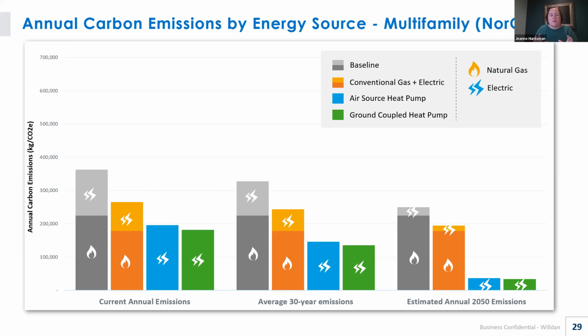So those bars show how things play out from a carbon emission standpoint for the current annual emissions with the grid we have today. As you can see, the lowest carbon output is the ground coupled heat pump system, followed closely by the air source heat pump, and you're using more carbon with the natural gas systems. Now, if you look at what the average emissions are expected to be over 30 years, with the projects already in place to clean the grid up over that time span...